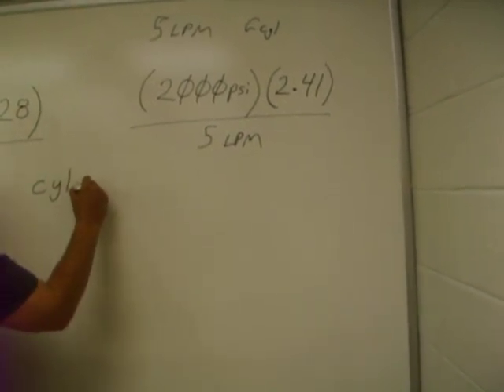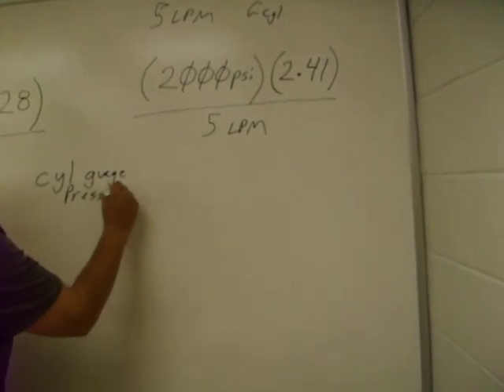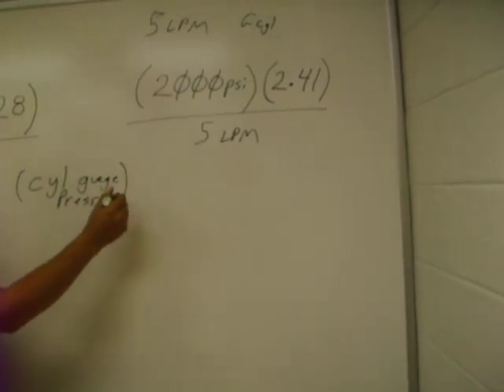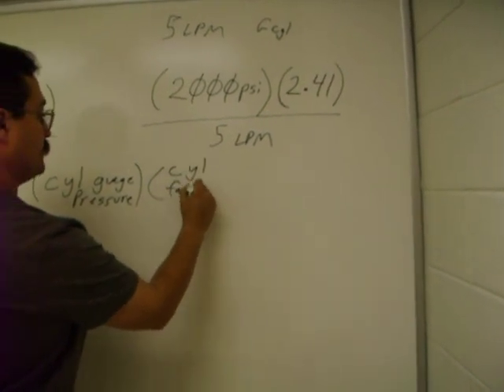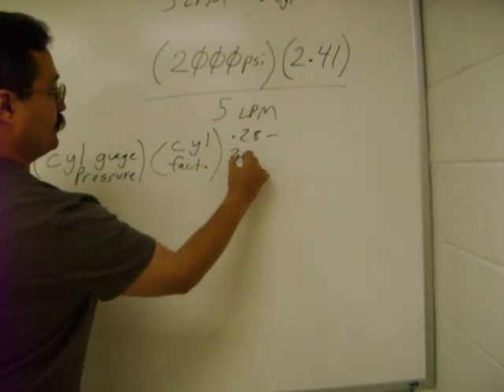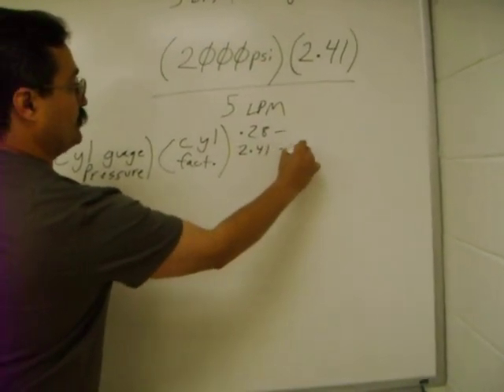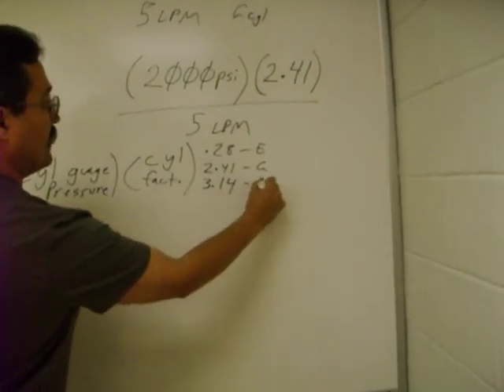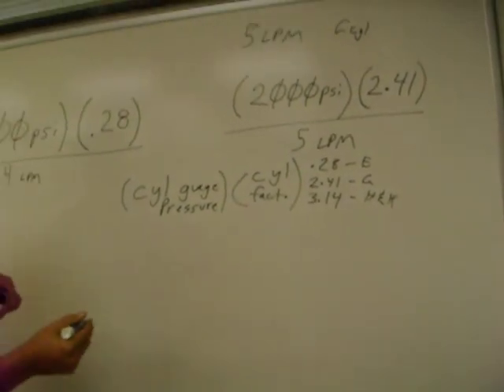The equation's always the cylinder gauge pressure times a cylinder factor, which is either 0.28 for an E-cylinder, 2.41 for a G-cylinder, or 3.14 for an H/K cylinder. Yes, these values are all for oxygen and air-filled tanks.